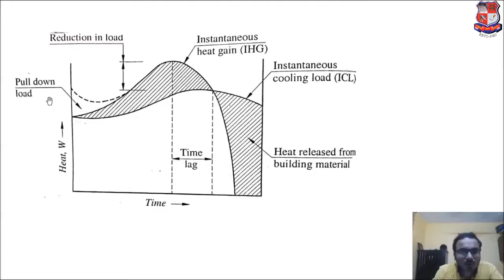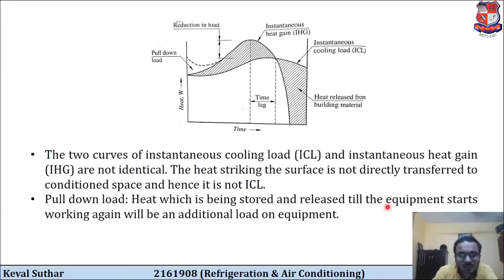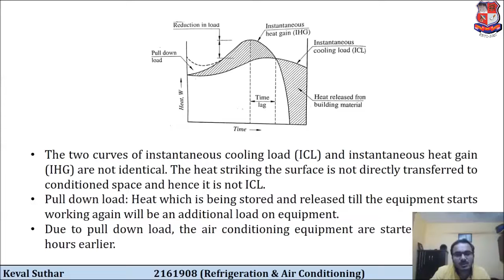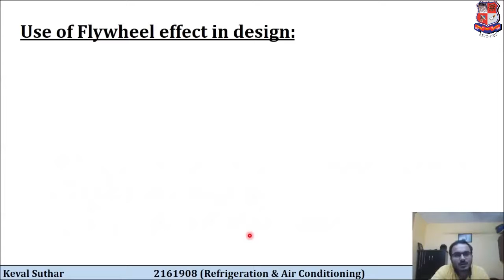Now we will study about pull down load. The heat which is being stored and released till the equipment starts working again will be an additional load on the equipment. So once we switch on the equipment, it doesn't immediately start the cooling effect. There will be some time which is required. So during this time heat will be stored and released. So this will be the additional load on the equipment. Due to this pull down load, the air conditioning equipments are generally started about 1 to 2 hours earlier. That is the effect of pull down load.